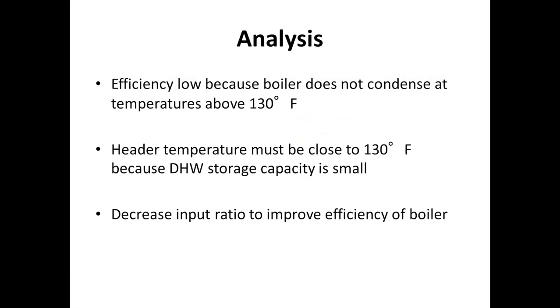mode. This building's heating also did have a domestic hot water heat exchanger to it. It was a very small capacity. It wasn't enough to drop the temperatures lower than we anticipated. So ultimately, we could reduce supply temperatures and allow for return temperatures to come back a little bit lower so that the unit was in condensing mode.